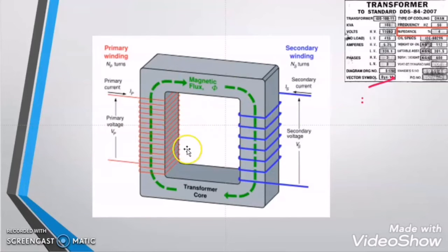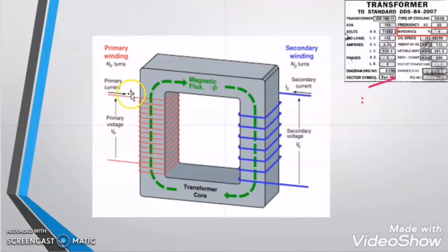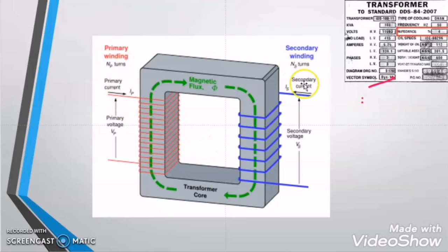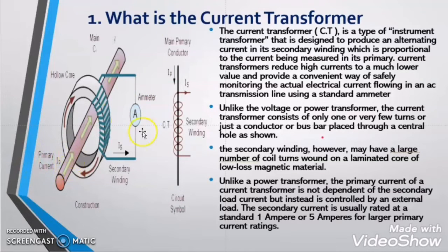Another big difference: in the power transformer the secondary current depends on the primary current and the primary current depends on the secondary current — there is a mutual relation. But in the current transformer the secondary current depends on the primary conductor, while the primary current does not depend on the secondary current. Even if we short or apply any other load to the secondary winding of the CT, the primary current will remain the same, as it is independent of the secondary winding.